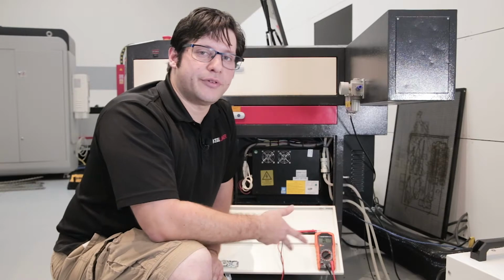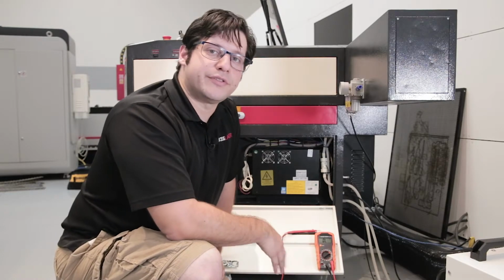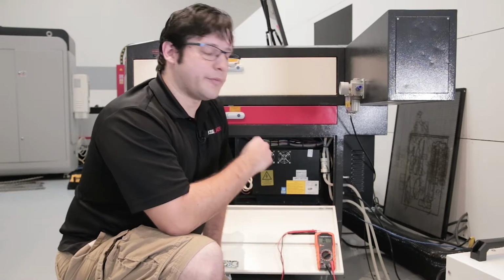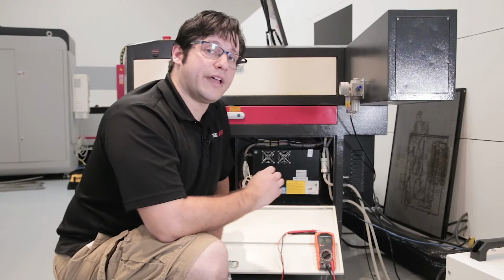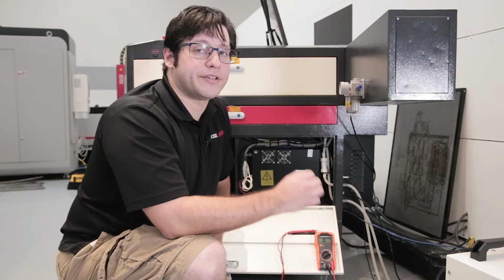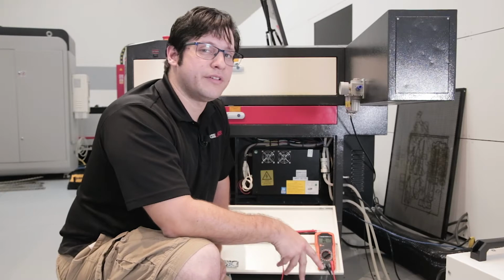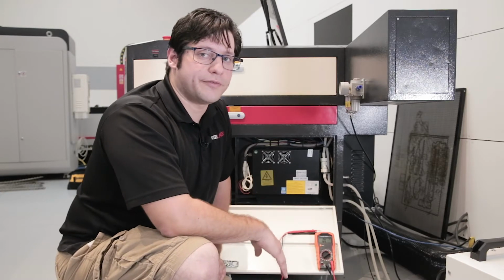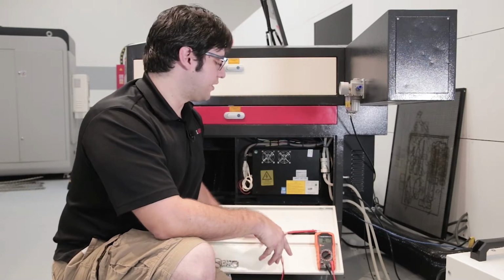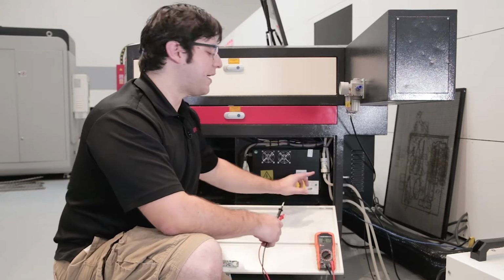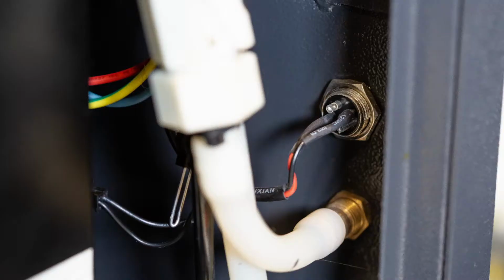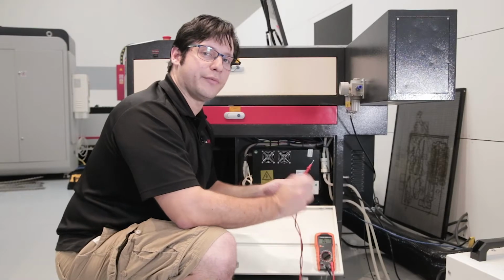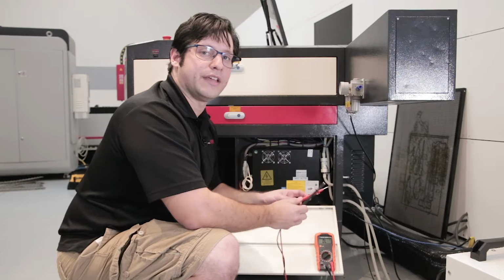After checking the first 2 interlocks, we're going to be at the third one, which is your chiller signal. So when we're checking this, we're going to go ahead and check for continuity as well. You're going to make sure that you have your water chiller on, but you want to have your machine off to check for continuity. You're going to take your prongs, and on the back of the plug that goes for your chiller signal, there's going to be 2 wires that plug in. You're going to take both of your prongs and place one of the prongs on each of those wires and check for continuity.